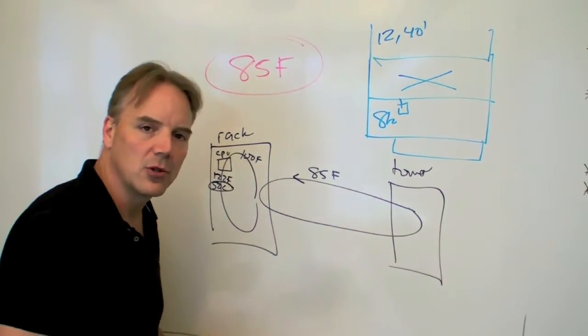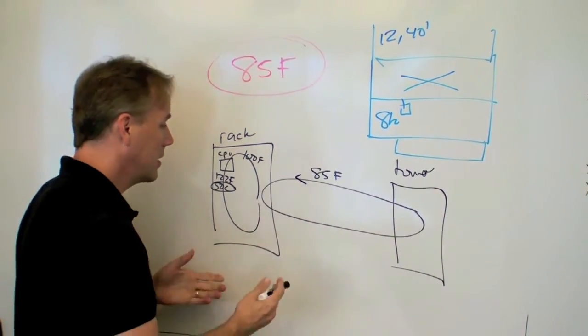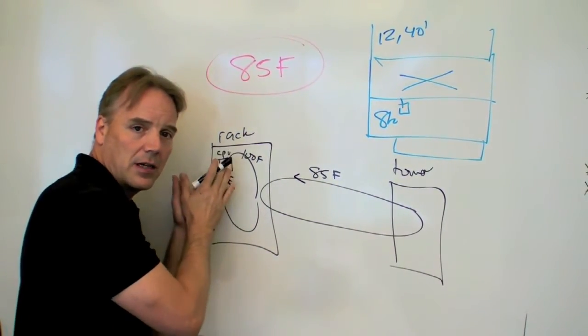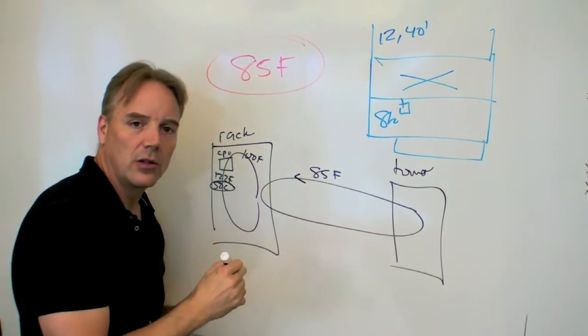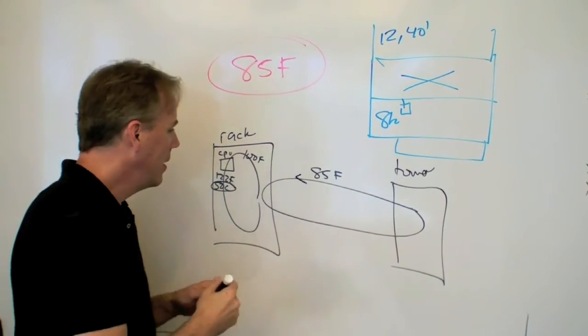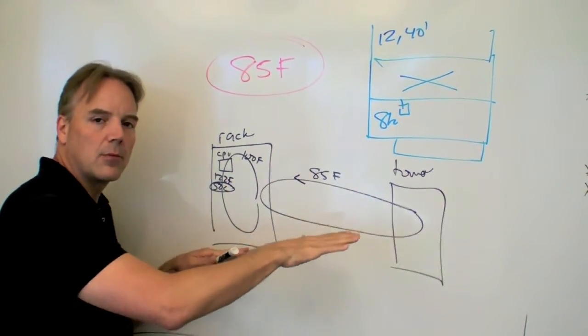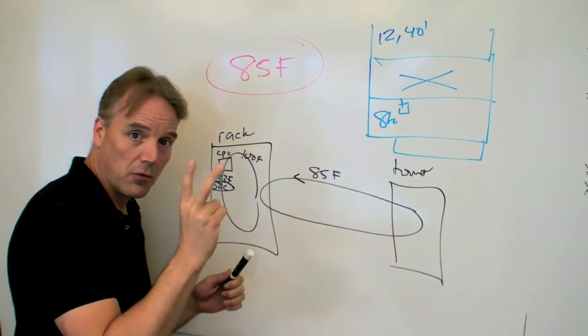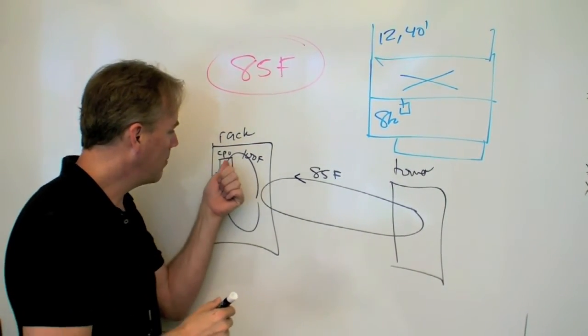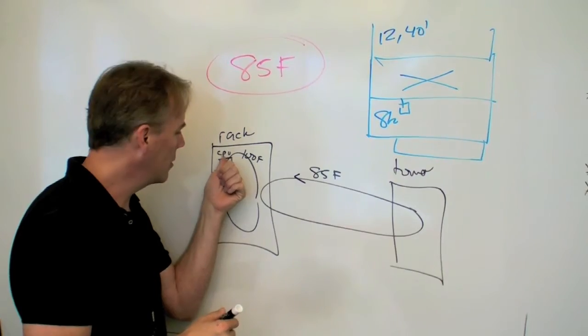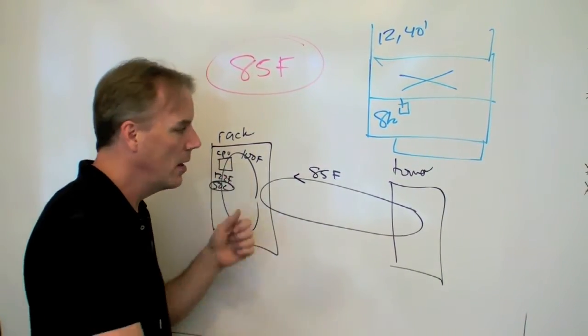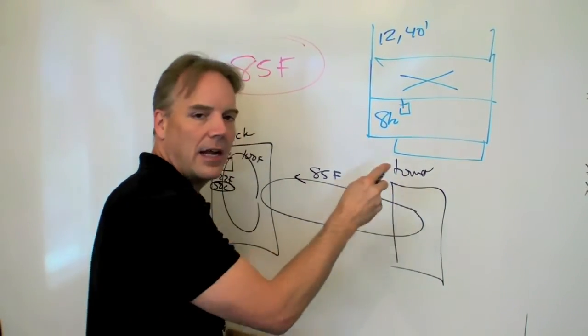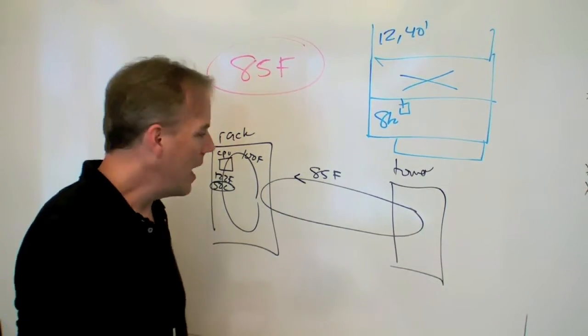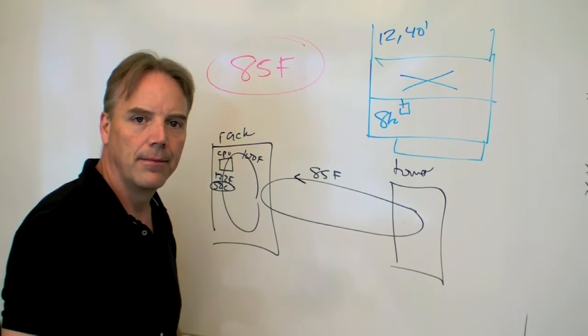What is the optimum temperature for that CPU? The main point is I can run this hotter as long as I've got closely coupled cooling, meaning that I'll have liquid cooling to that chip. This is kind of an end state, so that we can now optimize the performance of the system. But the two parameters I'm looking for: how do I get the optimized temperature for the CPU, and then the optimized outside air temperature for free cooling. Everything else can design around that.